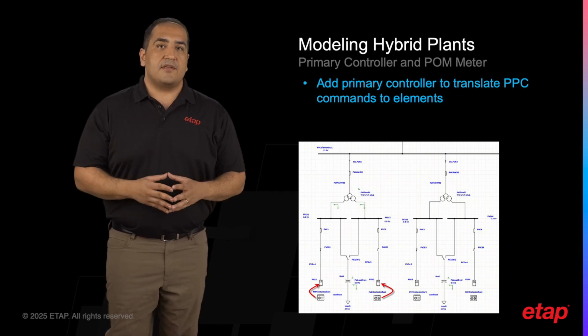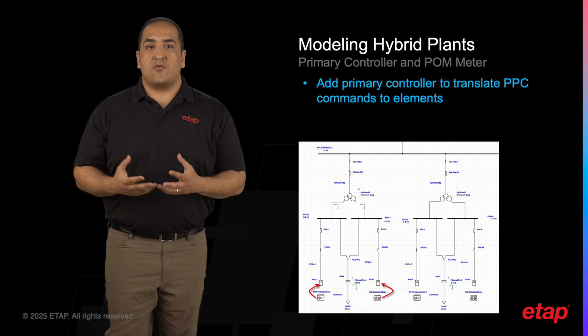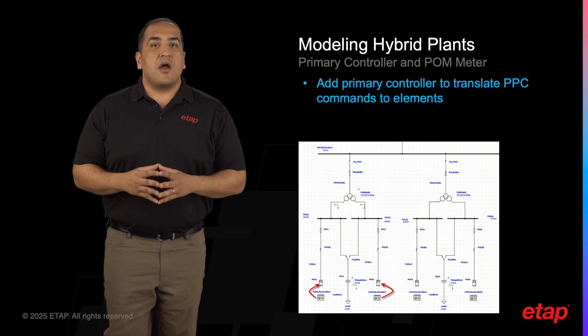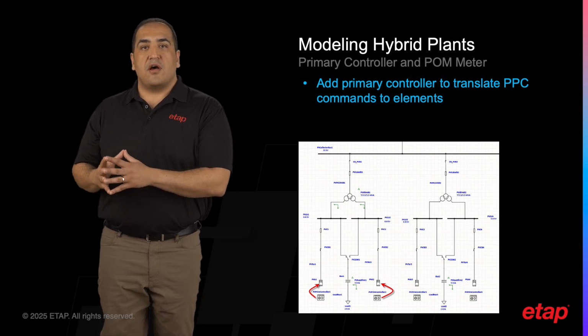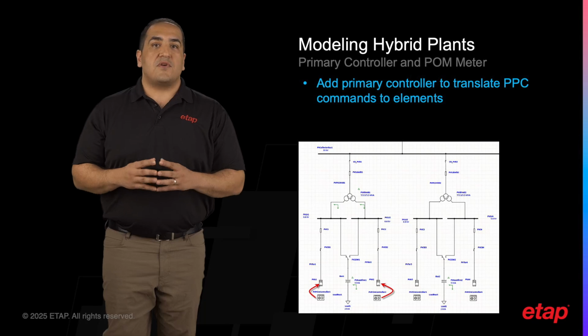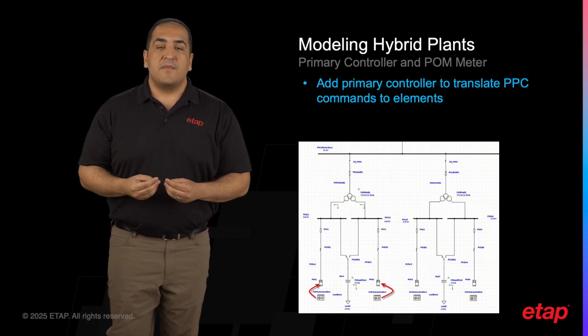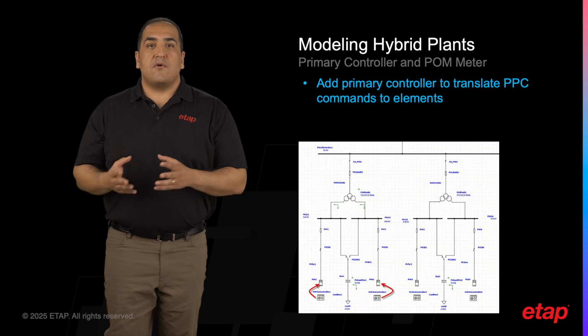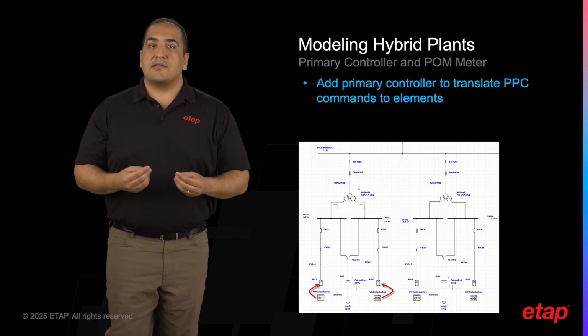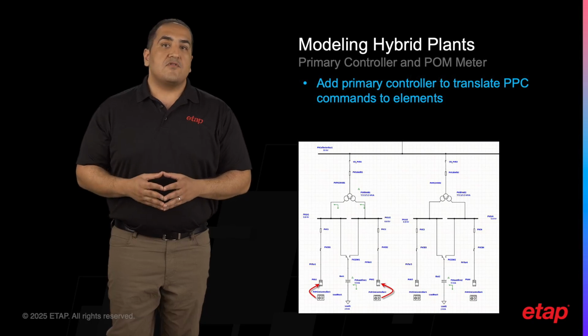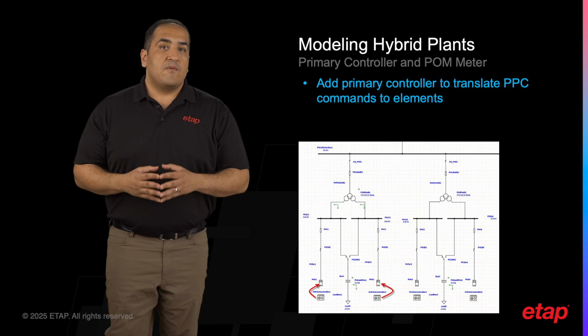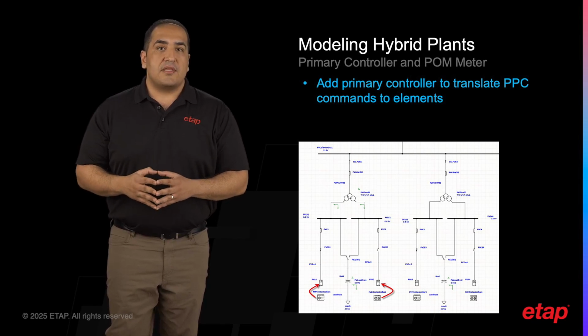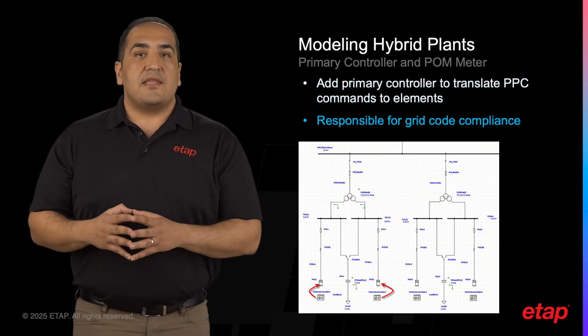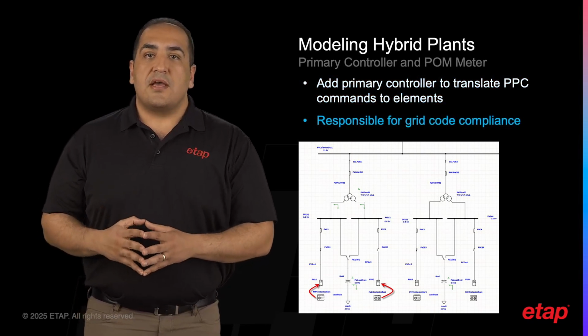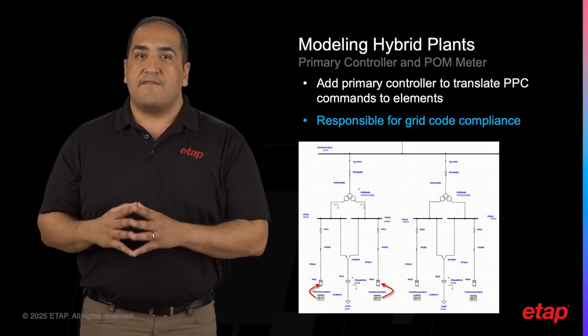After integrating these elements into the model, primary controllers and the point of measurement or POM meter can be introduced. Primary controllers are essential as they manage the control of individual power sources. Their main role is to translate commands from secondary controllers like EPPC into actionable control signals for electrical components. For example, they might convert active or reactive power set points into inverter currents or exciter and governor control signals. ETAP also provides a unique controller for the POM meter, which is needed for collecting all necessary measurements at the point of interconnection. This data then is passed to EPPC, ensuring that it has real-time access to vital metrics needed to manage the power plant effectively.